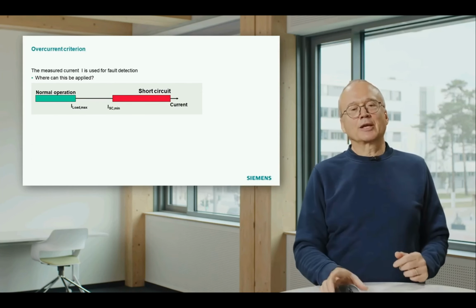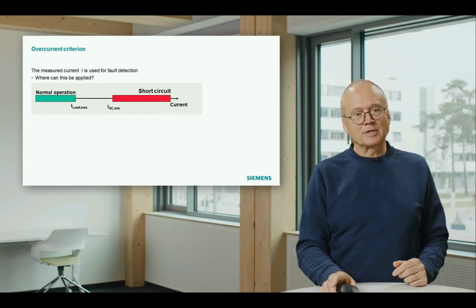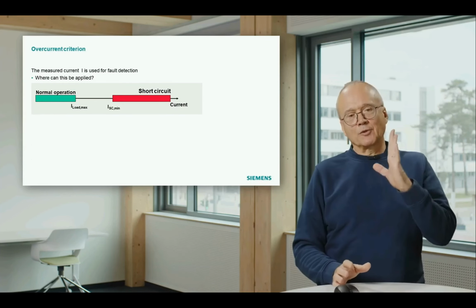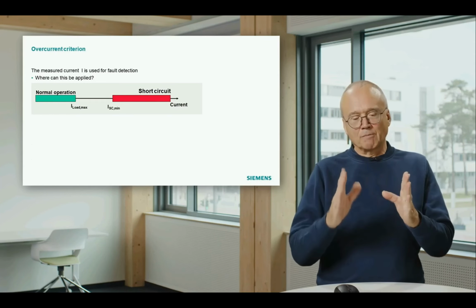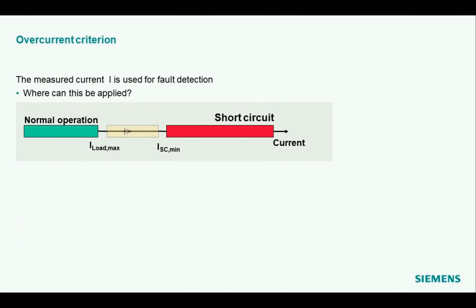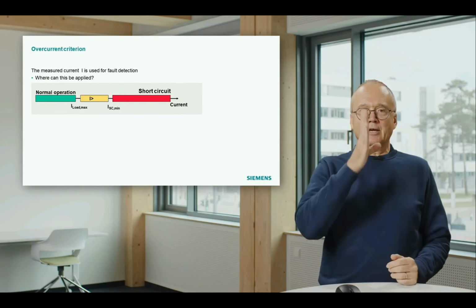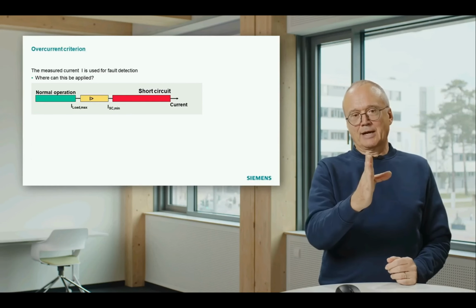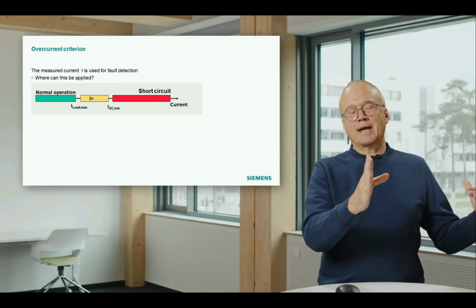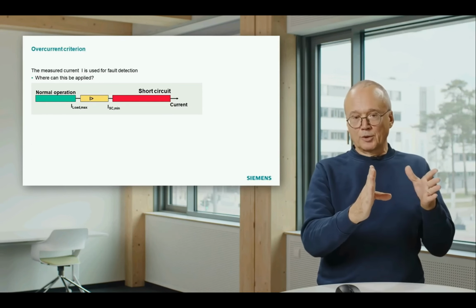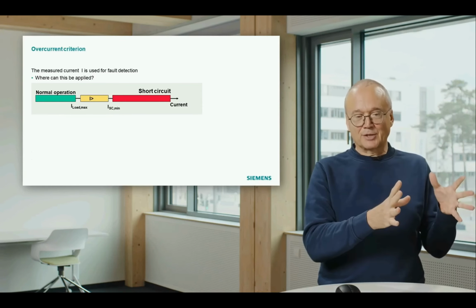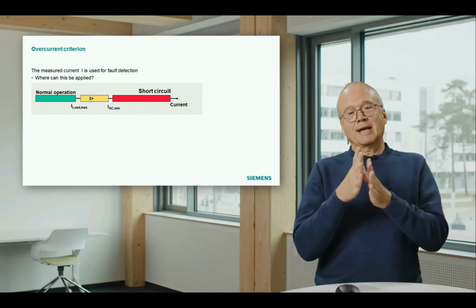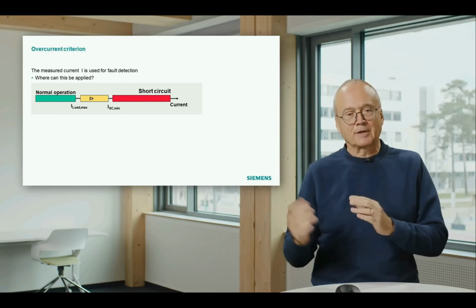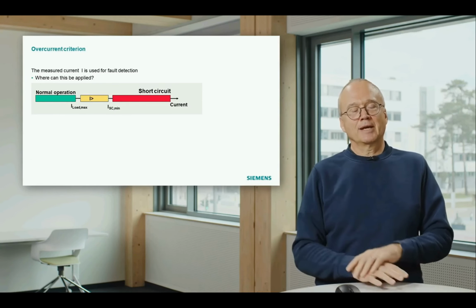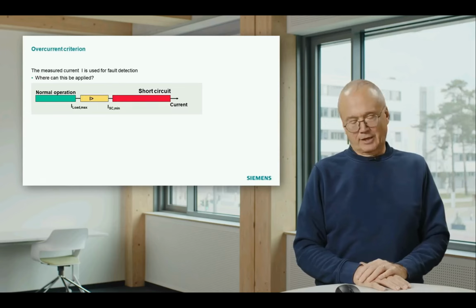And if we now see that we have a gap, as in this diagram, between the maximum load current and the minimum short circuit current, then we can make a setting somewhere in between and say, okay, in this gap I define a limit, and as long as the current is below this limit, I consider this as normal operation, and as soon as the current is above that limit, I consider that as a short circuit and will react on that.